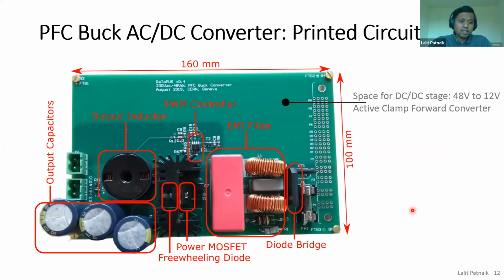That is one. The second would be the amount of derating you have in terms of temperature of operation and voltage of operation. So we use 100-volt capacitors, whereas the nominal operation is at 48 volts, so there is again a big derating factor there. And in terms of temperature, with respect to the 105 degrees Celsius rating of the capacitors, if we operate at say 45-50 volts, 50 degrees Celsius or so, again we have a big derating there. These are the only ways we can get around the problem of the reliability, or lack thereof, in electrolytic capacitors.